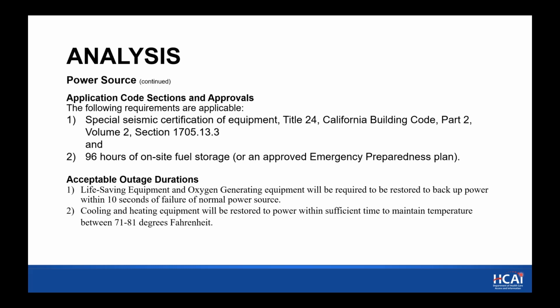Acceptable outage durations. We've included in the PIN that for life-saving equipment and oxygen generating equipment, power must be restored within 10 seconds of failure to the normal source. And for cooling and heating equipment, power will need to be restored within sufficient time to maintain the temperature range of 71 to 81 degrees Fahrenheit.